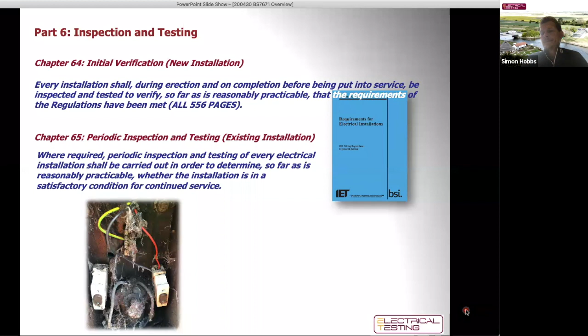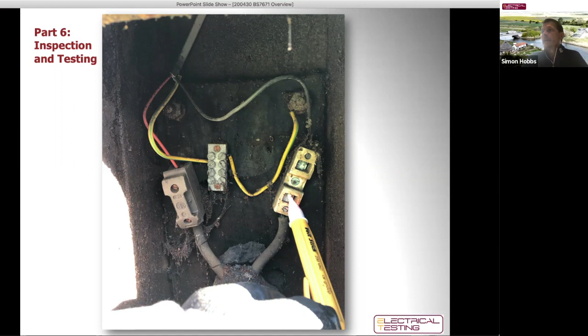So what sorts of things might we find in an inspection? This is a volt stick, a handy tool, an unapproved test instrument, but very handy. You can see it's lit up here, on the neutral end. So we've got a lovely reverse polarity in this installation. That's a Code 1 defect, something that needs to be dealt with immediately. You can find those during inspection.